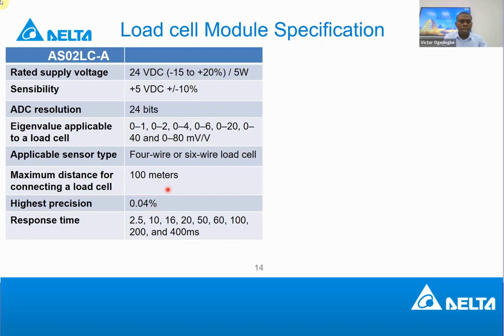You multiply this with the Eigenvalue and the excitation voltage to see how accurate the reading that the load cell module is reading, how accurate it is. And then you also have the response time. So this response time is the time it takes the load cell module to read the weight, the load signal, the weight signal that is coming from the load sensor.